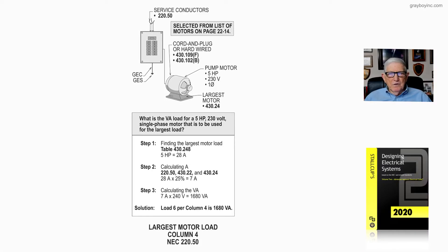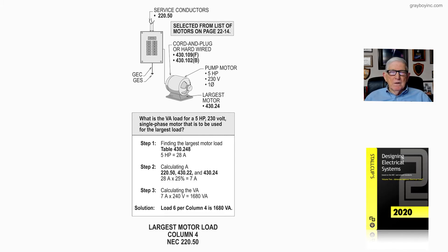Now let's take a look at figure 22-17, which deals with determining the largest motor load in the column, in accordance with 220.50. If you stayed with us through these calculations, we have columns 1, 2, 3, and 4, where these loads are placed in columns so that you keep your loads straight.